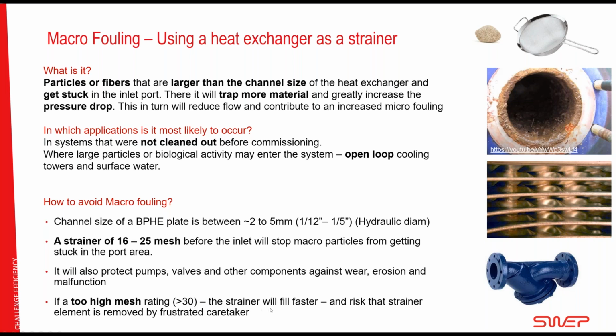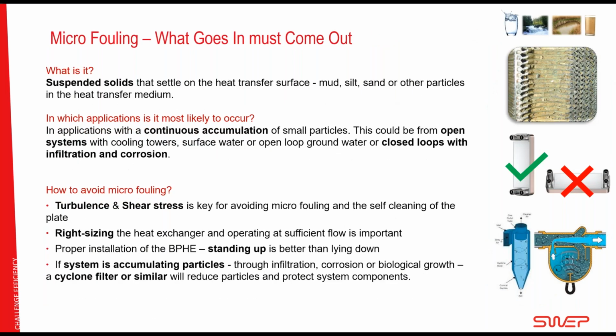What will happen then is the strainer will fill up faster, and there is an increasing risk that the more fine strainer will cause frustration for the caretaker. So that person, instead of cleaning it once a month or once every quarter, has to do it so often that he says, screw it, I take it away. It shouldn't happen. It does happen. So use a strainer, yes. Don't use too much.